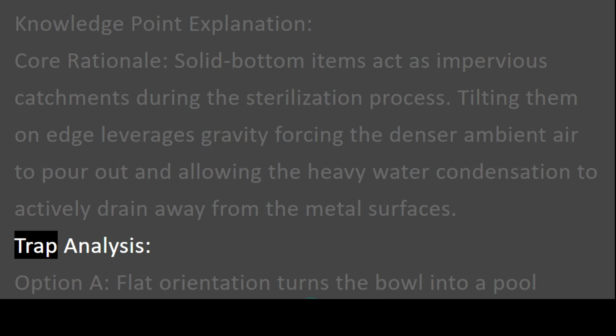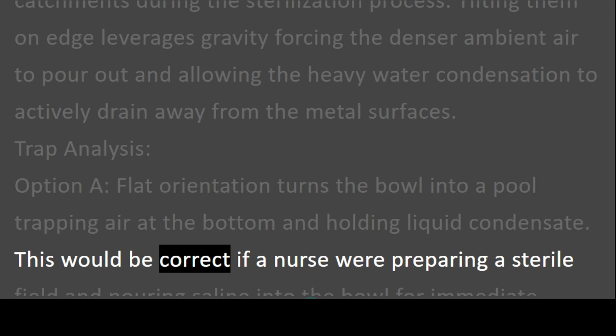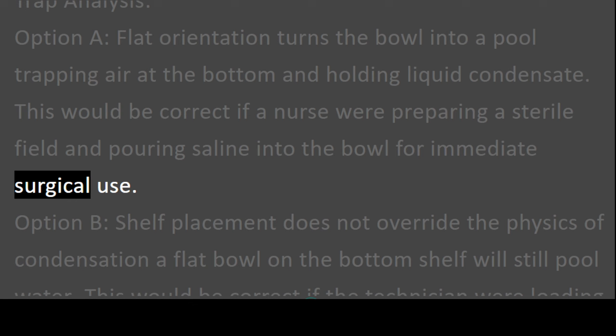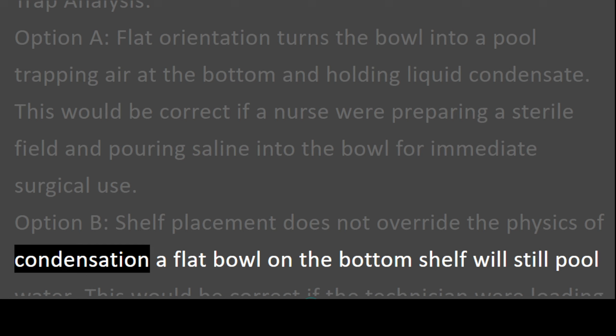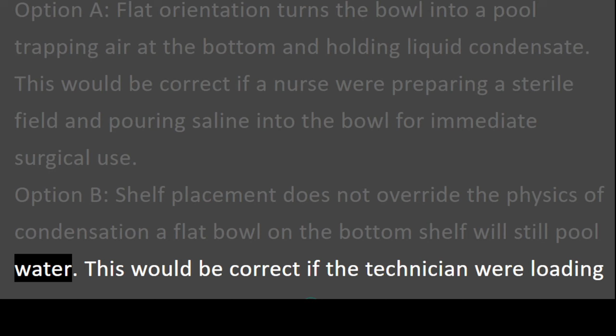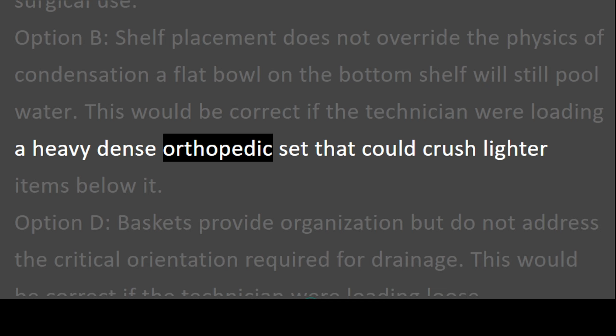Trap analysis. Option A. Flat orientation turns the bowl into a pool, trapping air at the bottom and holding liquid condensate. This would be correct if a nurse were preparing a sterile field and pouring saline into the bowl for immediate surgical use. Option B. Shelf placement does not override the physics of condensation. A flat bowl on the bottom shelf will still pool water. This would be correct if the technician were loading a heavy dense orthopedic set that could crush lighter items below it. Option D. Baskets provide organization but do not address the critical orientation required for drainage. This would be correct if the technician were loading loose disarticulated instrument clamps into a mechanical washer disinfector manifold.